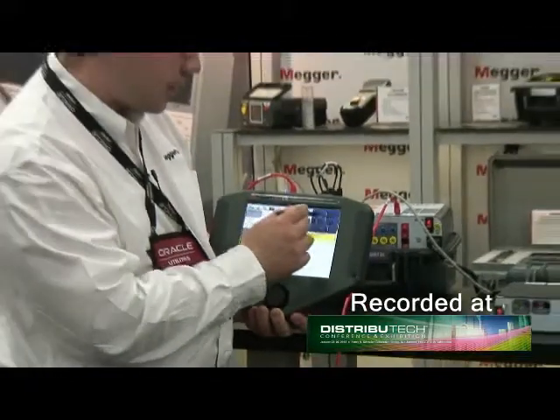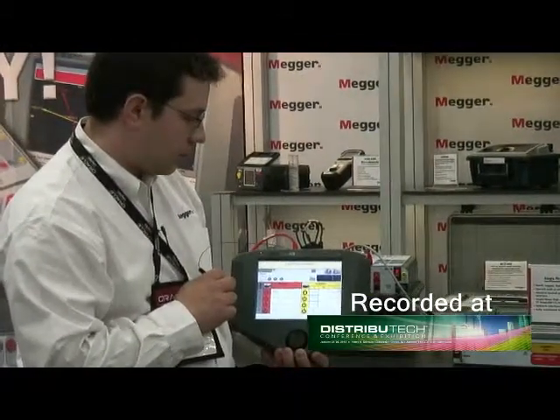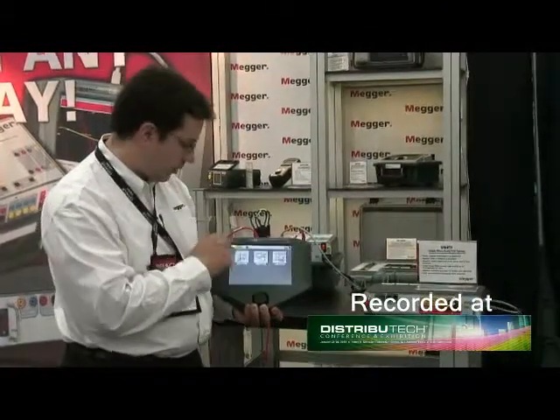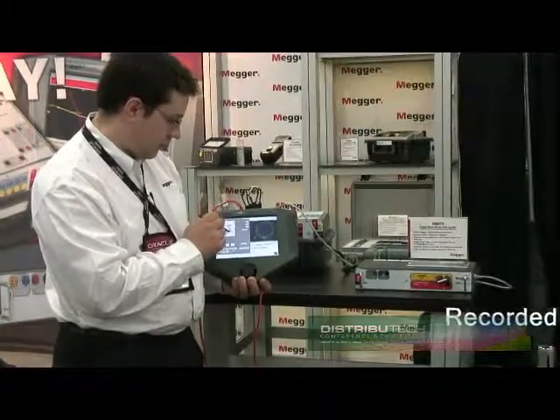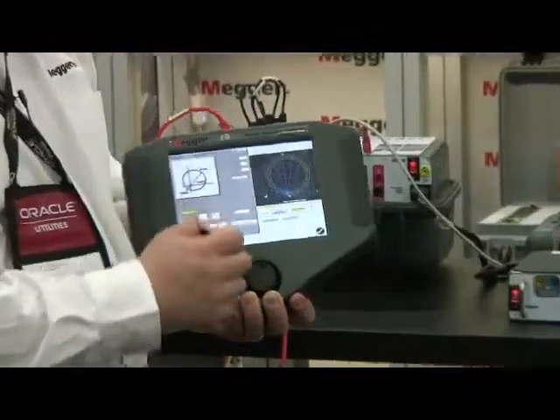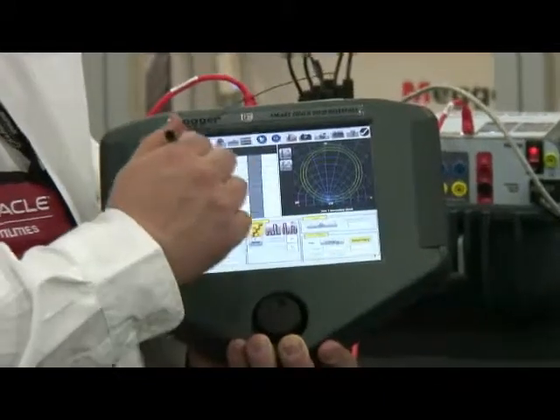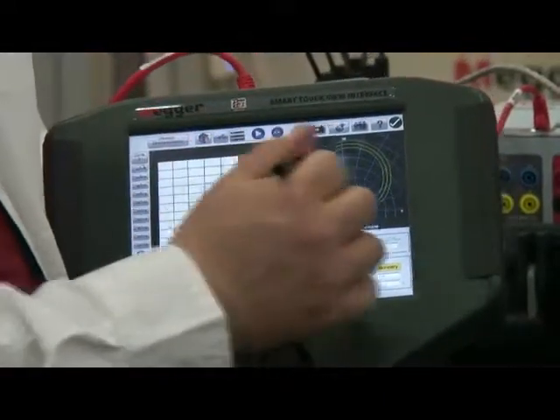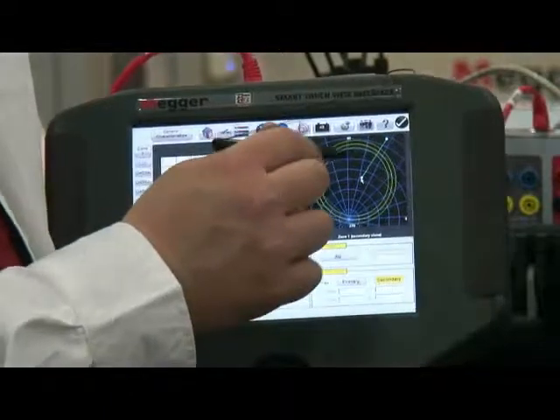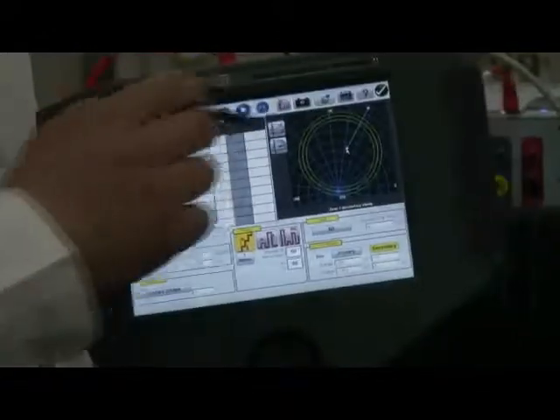We've also added the functionality of testing line distance relays straight from the STVI interface. If I go to a generic characteristic and select a Mho circle, I can put in the reach, angle, offset, each of the zones of protection, and the type of fault I'm going to apply. I hit OK and then select the points that I need to test. Here's my test point — the currents and voltages will ramp in until the characteristic picks up, and I've tested my distance relay.